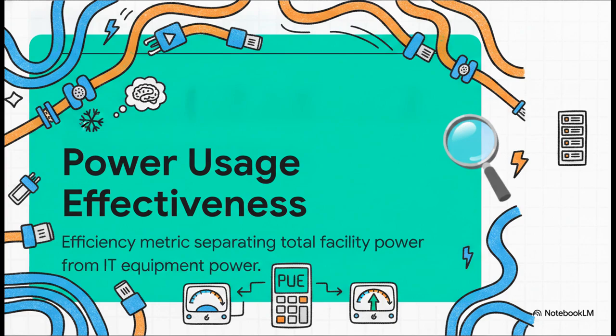So, the absolute crucial point is this. Why go through all this meticulous trouble to clamp every different type of cable in the building? Well, it's primarily for PUE, or power usage effectiveness. This is the ultimate grading metric for a data center. By having specific clamps dedicated to the cooling systems and separate clamps dedicated to the IT racks, the software can explicitly separate the total power the facility uses from the power used just for computing. Without that distinct separation, you just cannot accurately calculate PUE, which means you can't prove to the market how efficient and optimized your AI factory truly is.